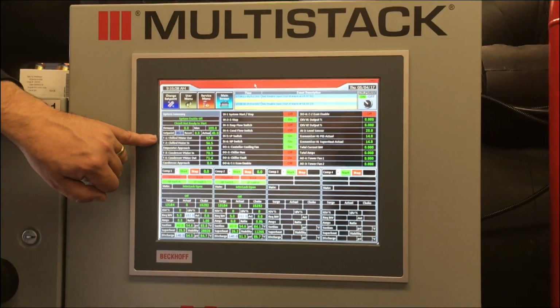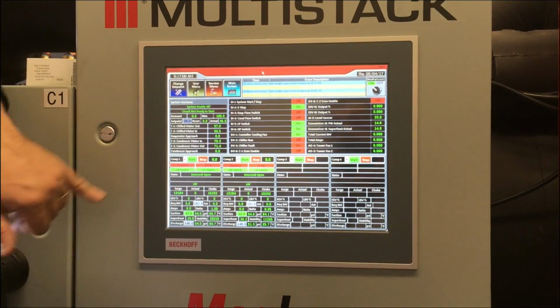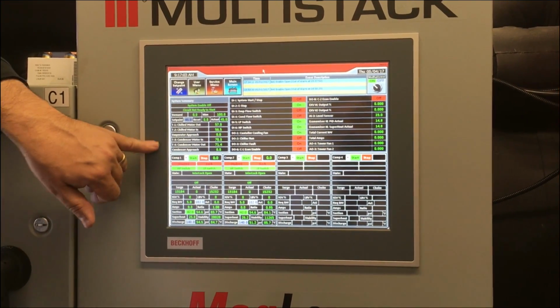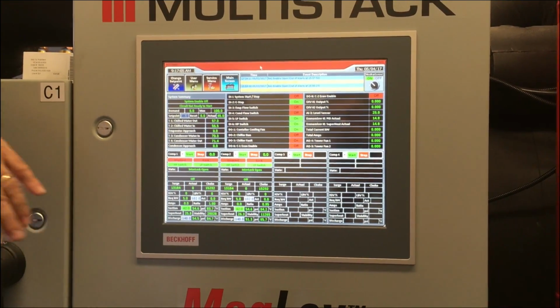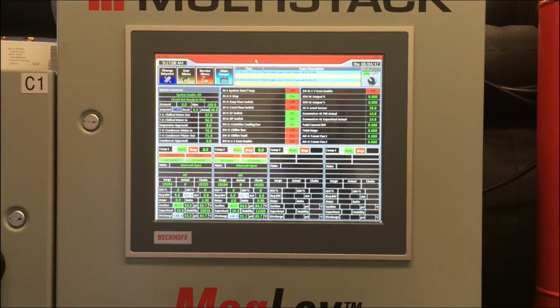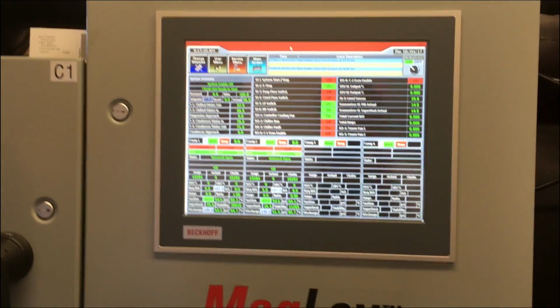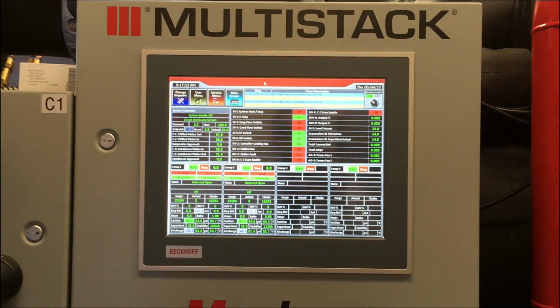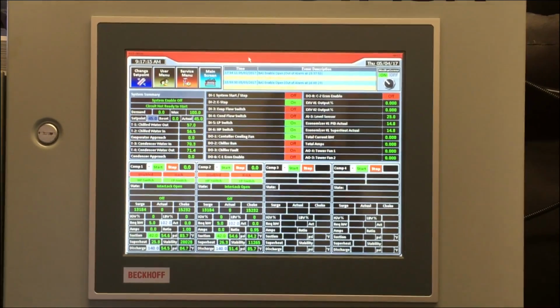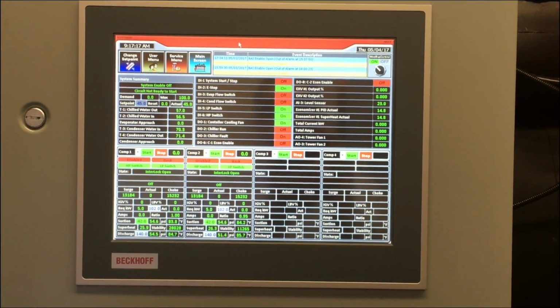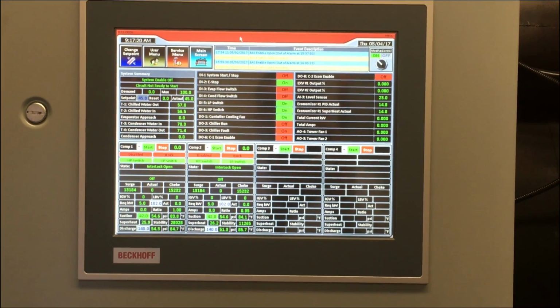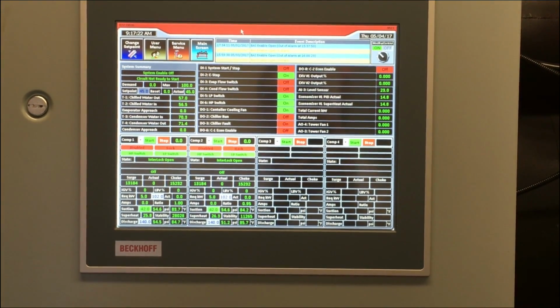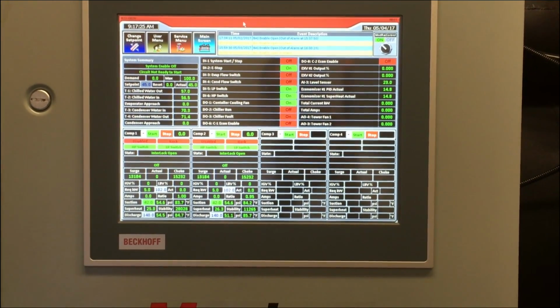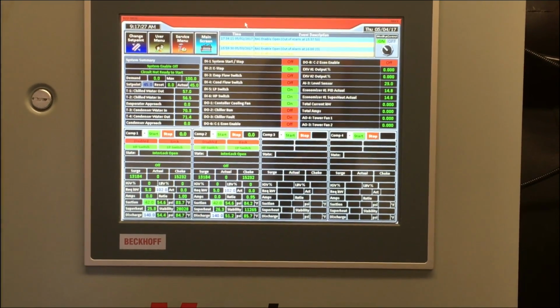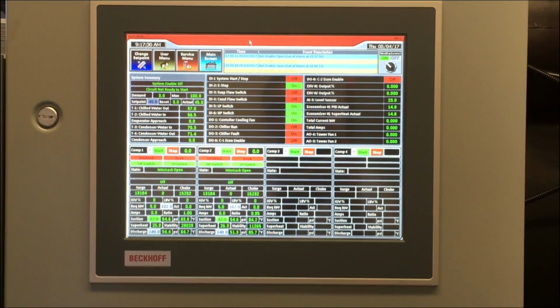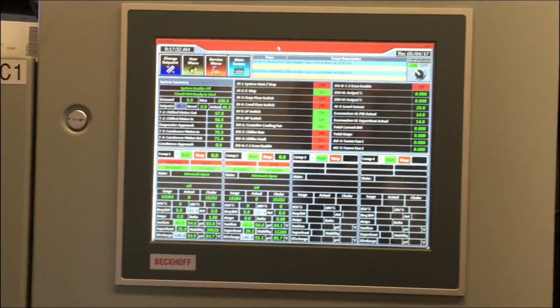So we have chill water out, chill water in temps, we have evaporator approach, and then we have condenser water in, condenser water out, and condenser approach. Approaches are the difference between, it's like superheat, but it's on water instead of Freon and suction. So it's the difference between leaving chill water temp and suction temperature. So we want that to be pretty close, 1, 2, 3, somewhere in that ballpark. If it gets too far out, we're not very efficient, which means we're either low on gas or we're maybe moving water too quickly, so we're not picking up as much heat as we should, or the chill's dirty, so it's not transferring heat as effectively, things like that.